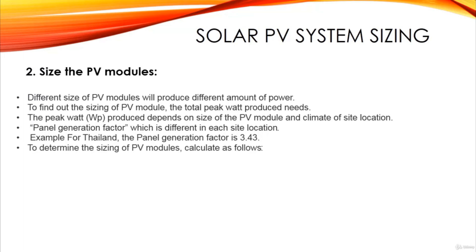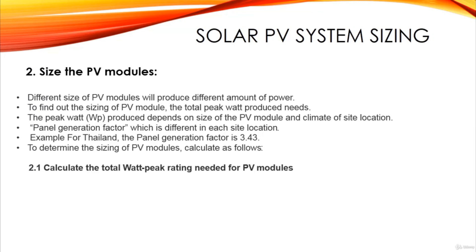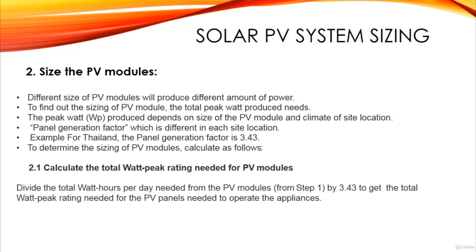To determine the sizing of the PV modules, calculate as follows. Step one: calculate the total watt peak rating needed for the PV modules. From our previous step, we found the total watt hours needed per day. We will divide the total watt hours per day by 3.43 — the panel generation factor — to get the total watt peak rating needed for the PV panels.